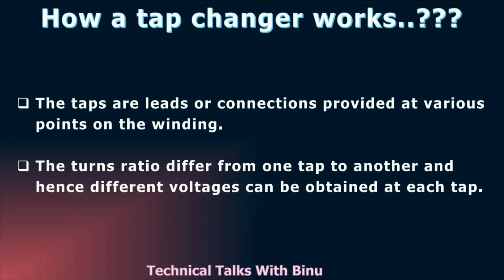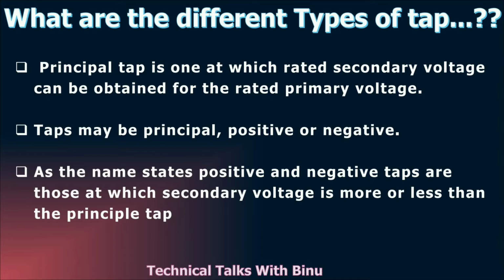Now we will see how a tap changer is controlling the output voltage. Taps are basically leads or connections which are provided in windings. Turns ratio will be varying from tap to tap and hence different voltages are obtained in each tap. Up next are the different types of tap. Principal tap is a tap at which rated secondary voltage can be obtained for the rated primary voltage. Taps can be principal, positive or negative.